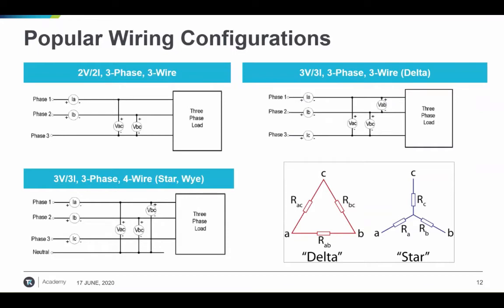There is a 2V2I configuration — whenever we say 2V2I or 3V3I, that means you're using two voltage probes and two current probes, or three voltage and three current probes, to make the connection for measurement. A 2V2I configuration utilizes two voltage and two current probes to make three-phase measurements, also called the two-watt meter method. It uses two voltage measurements referenced to the same phase or line and the two currents flowing into that phase. The assumption is that the three-phase system is balanced — the summation of all voltages at neutral is zero volts and the summation of all currents is zero amps, true if there is no leakage current from neutral to ground.